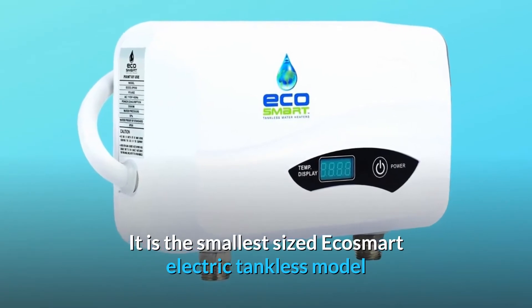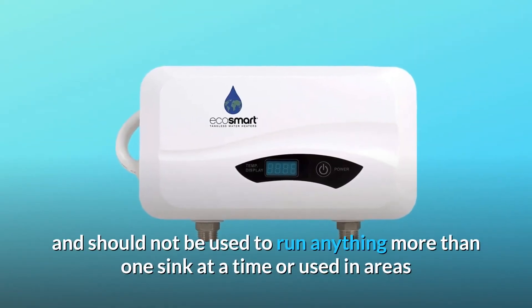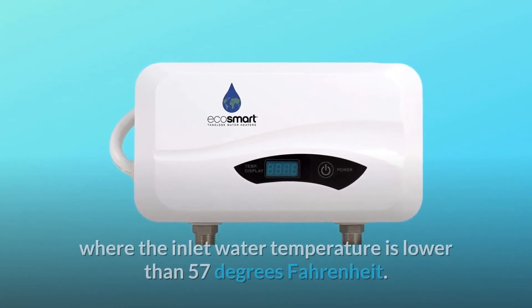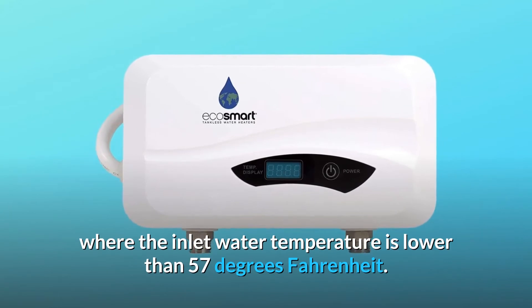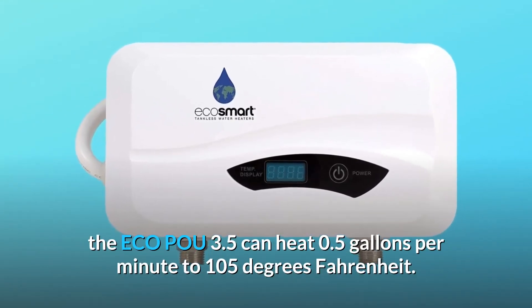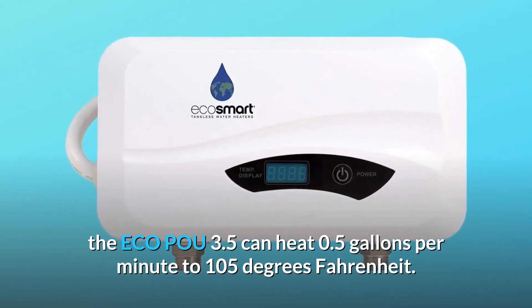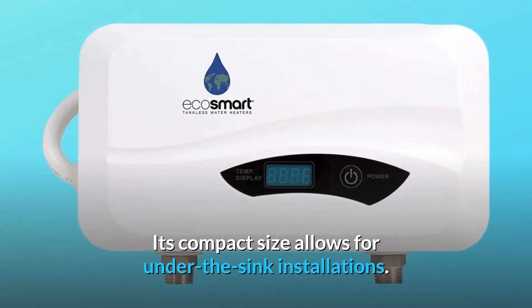It is the smallest-sized EcoSmart electric tankless model and should not be used to run anything more than one sink at a time, or in areas where the inlet water temperature is lower than 57 degrees Fahrenheit. At this inlet temperature, the ECO POU 3.5 can heat 0.5 gallons per minute to 105 degrees Fahrenheit. Its compact size allows for under-the-sink installations.